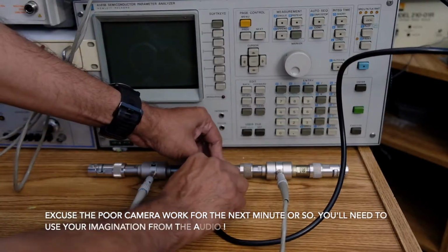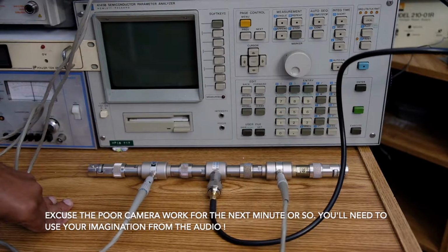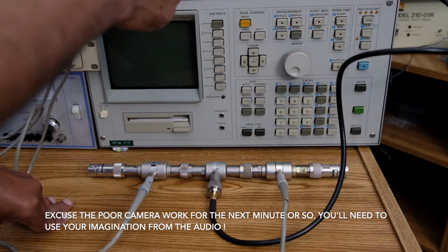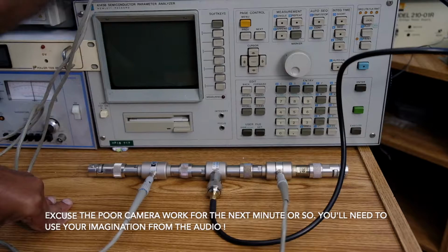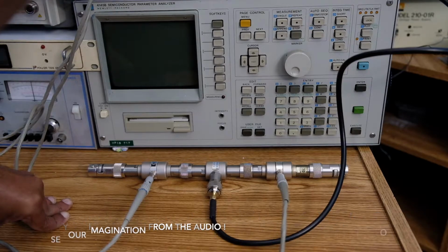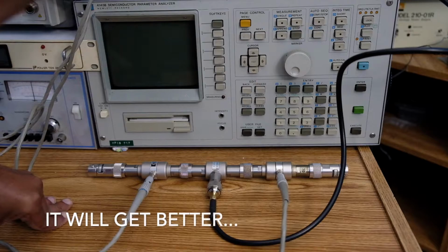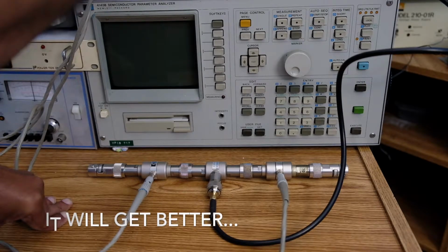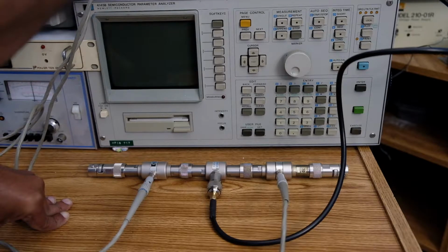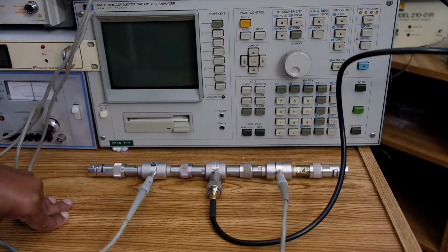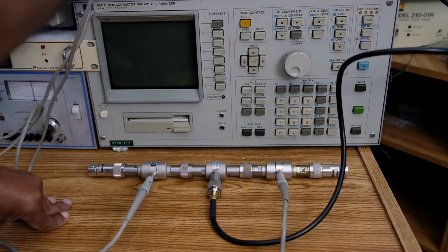As you can see right now, the vector voltmeter is not locked. It's a frequency sensitive instrument, so I've got to bring the frequency range to approximately the frequency that is being transmitted by this RF signal generator. So we're going to do that, and it will actually lock over a fairly wide range, so it's already locked, as you can see. But I'll just bring it to 20, which is a frequency that I am interested in, and just use it at this setting. Now the APC light that says unlocked is gone.